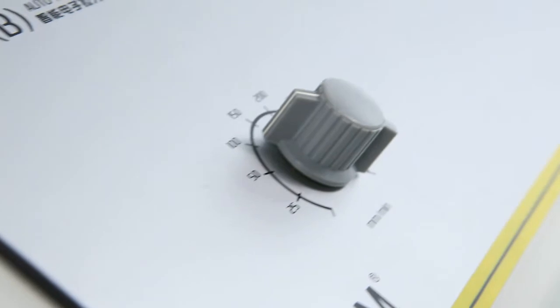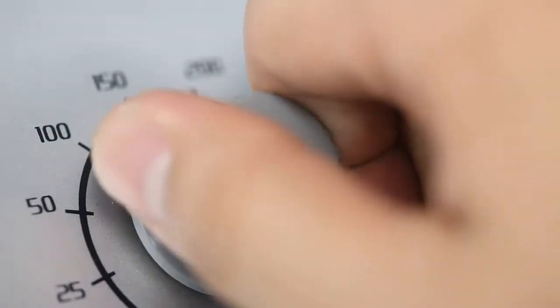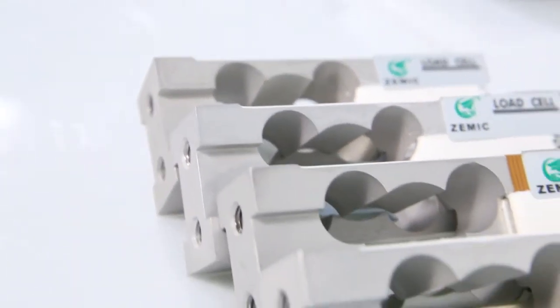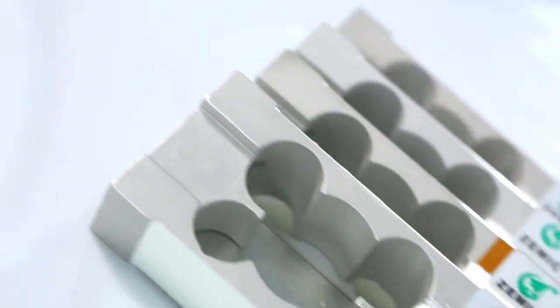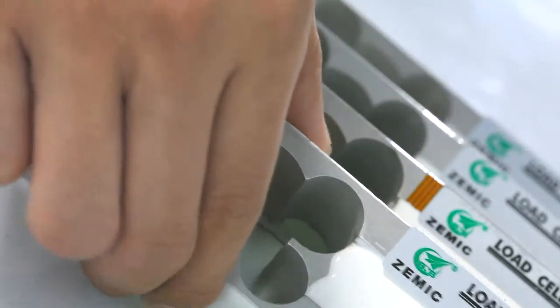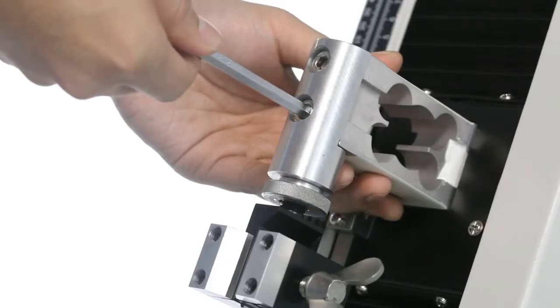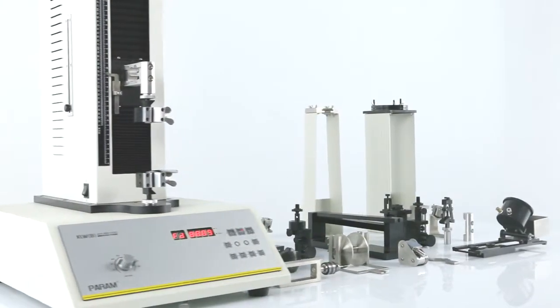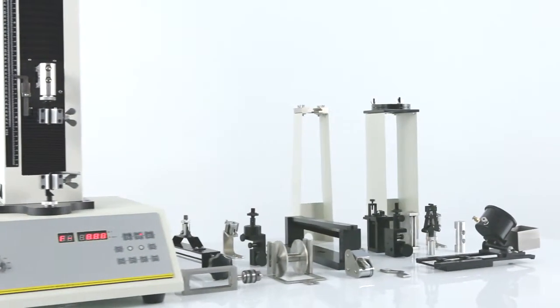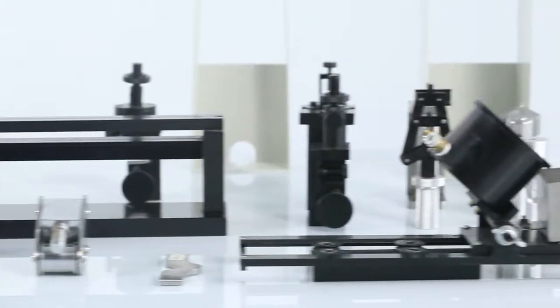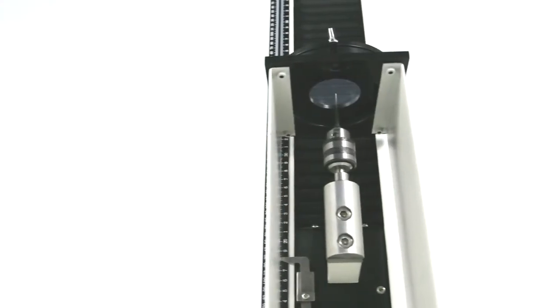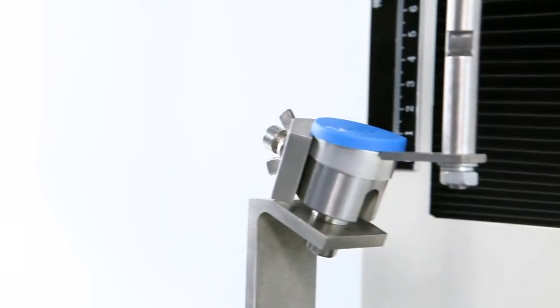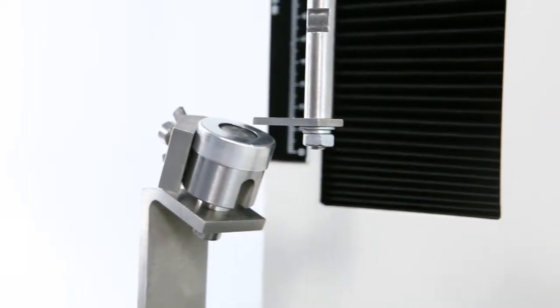The instrument can perform tests at seven different testing speeds that meet different industry standards. Four high precision load cells of 30N, 50N, 100N, and 200N can satisfy different testing requirements. With additional customized testing fixtures, the tester can perform a variety of special tests such as the puncture resistance of films and the opening force of bottle caps and many others.